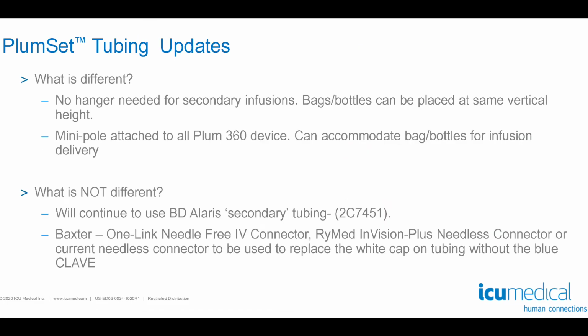Now let's talk about tubing. What is going to be different? Again, no hanger is needed for secondary infusions. Bags or bottles can be placed at the same vertical height as a primary infusion. Mini poles attached to the side of the Plum 360 device can accommodate bags or bottles for infusion. This means that we no longer have to hang infusions at 20 inches above the pump.